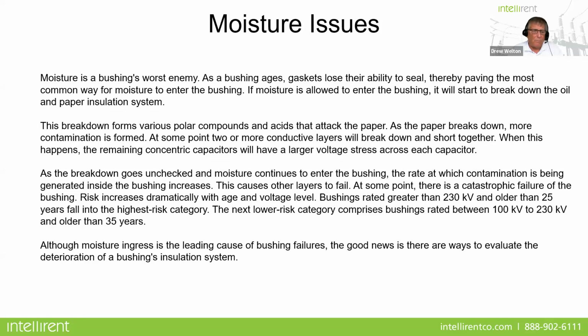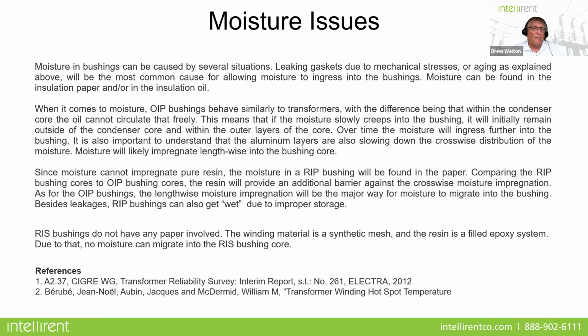So we know that if moisture ingress is the leading cause of bushing failures, there's good news: there is a way to evaluate the deterioration of the bushing's insulation system. Moisture in a bushing can be caused by several situations. Leaking gaskets due to mechanical stress or aging are the most common cause for allowing moisture to ingress into the bushings. Moisture can be found in the insulation paper or the oil.